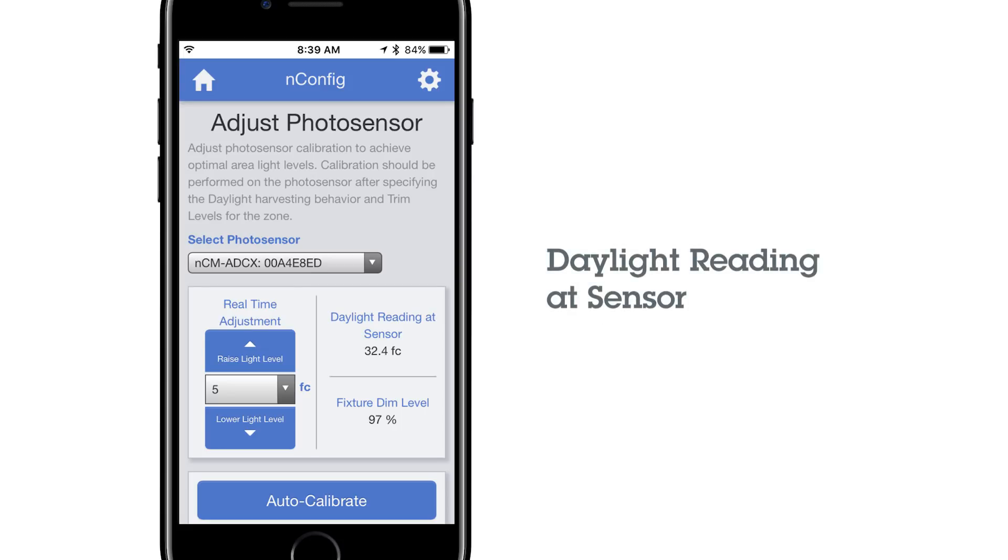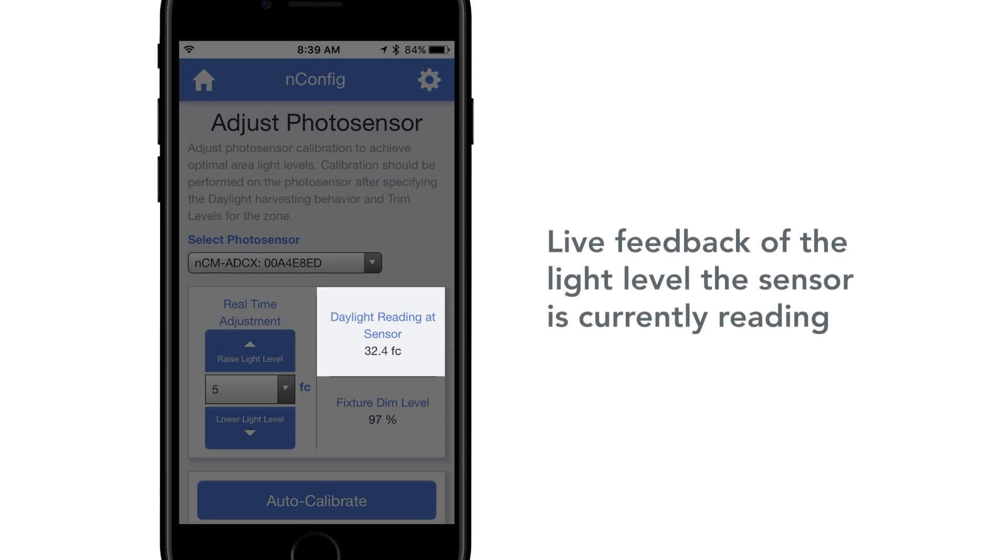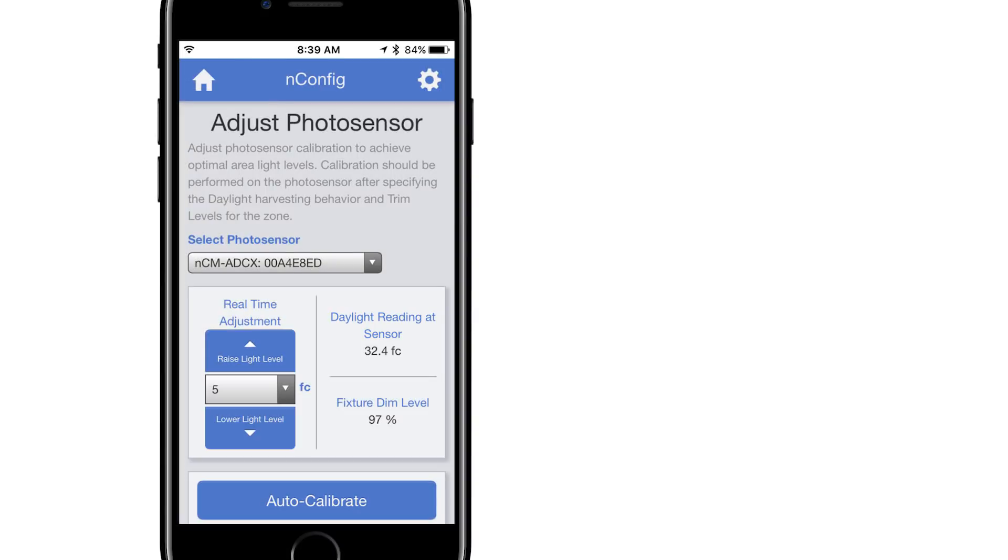Daylight Reading at Sensor. This is live feedback of the light level the sensor is currently reading. The sensor will be constantly adjusting the fixture dim level in very small increments based on this value, attempting to match the Daylight Reading at Sensor to the Real Time Adjustment value.